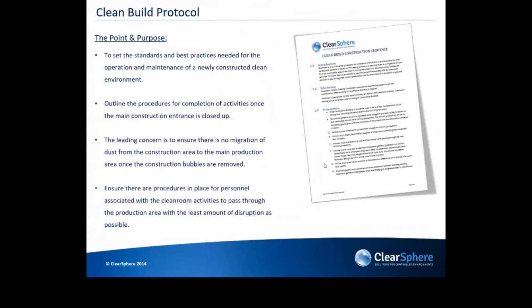We operate a clean build protocol system. The main purpose is to keep quality from the very get-go, getting the guys installing sockets and turning screws and nuts and bolts into the mindset of what we're actually building - a facility for producing drugs for very sick people, not just blocks and mortar. It's very important. It sets the standard and best practices needed for operation and maintenance of a newly constructed cleanroom environment, and outlines procedures for completing activities once the main construction building is closed. The leading concern is to ensure there's no migration of dust from the construction area into the main cleanroom production area once the construction bubbles are removed.